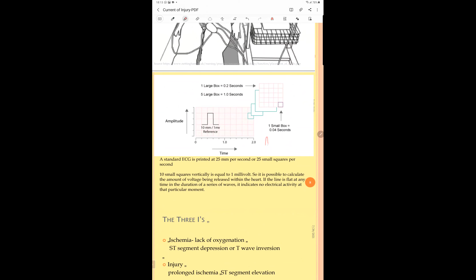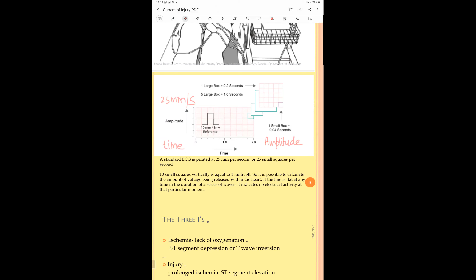300 per... Huh? 25 mm per second. Yes, 25 mm per second. So whenever we start recording ECG, we must remember that it is calibrated. The machine is calibrated. The speed of the paper is set at 25 millimeter per second, and the voltage is set at 1 millivolt per 10 mm.